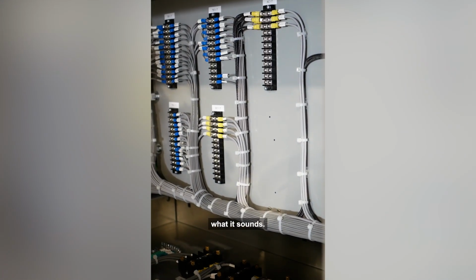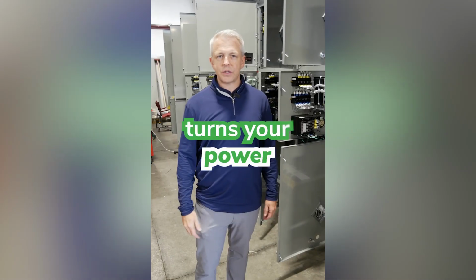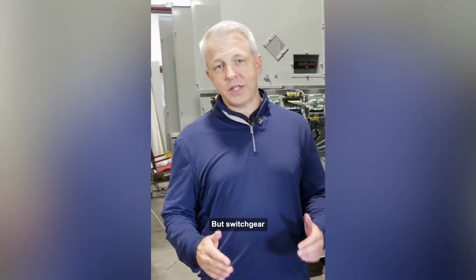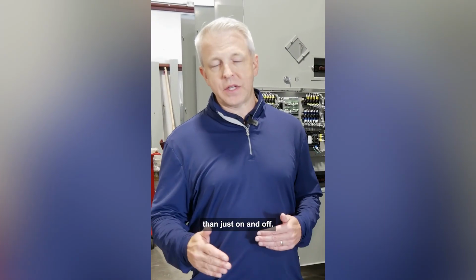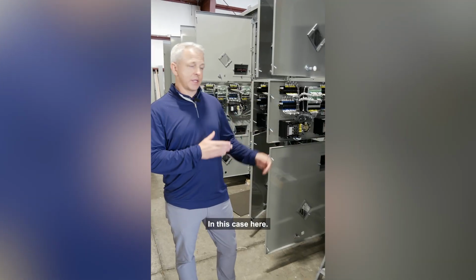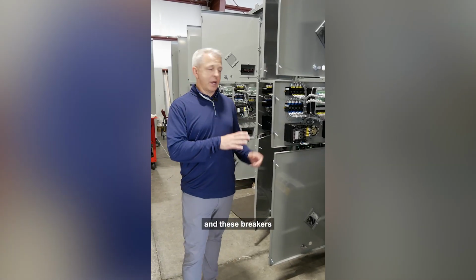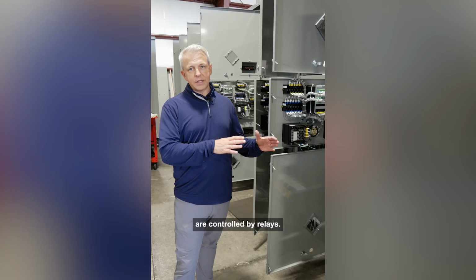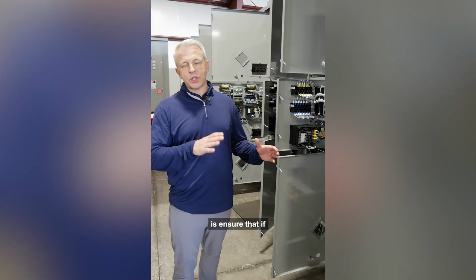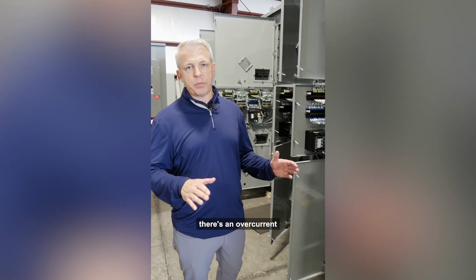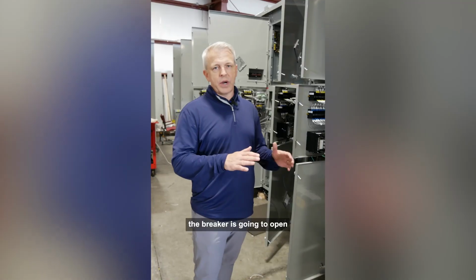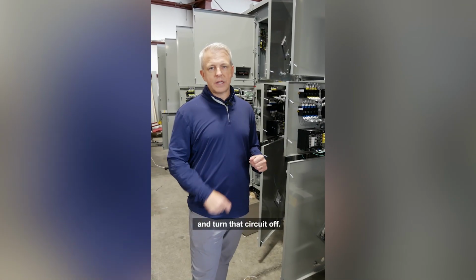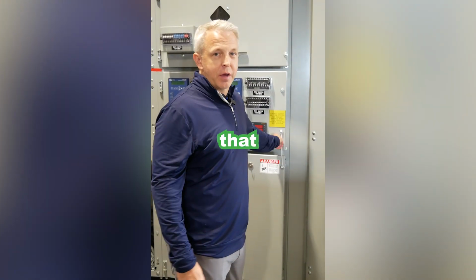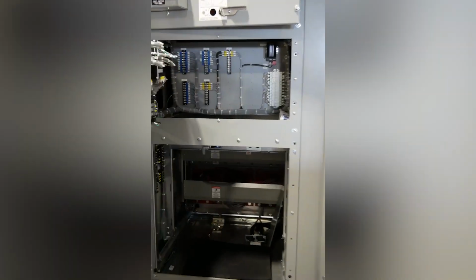Switchgear is exactly what it sounds like. It's a series of switches that turns your power on and off. But switchgear can get more complicated than just on and off. In this case here, there are breakers, and these breakers are controlled by relays. What the breakers are going to do is ensure that if there's an overcurrent situation, the breaker is going to open and turn that circuit off. This is a part of the switchgear that most people never get to see.